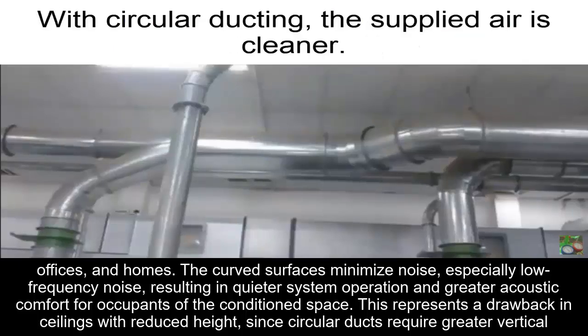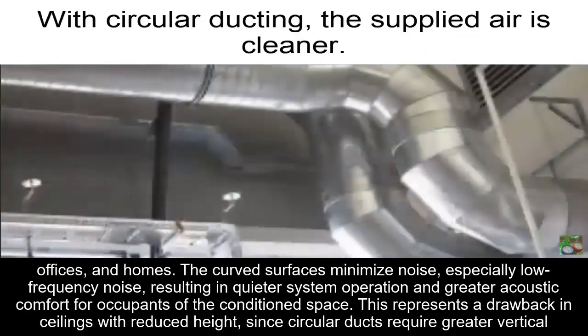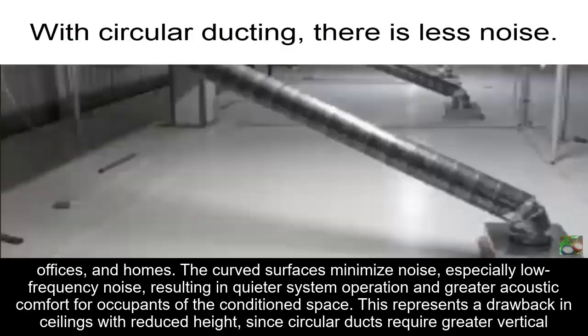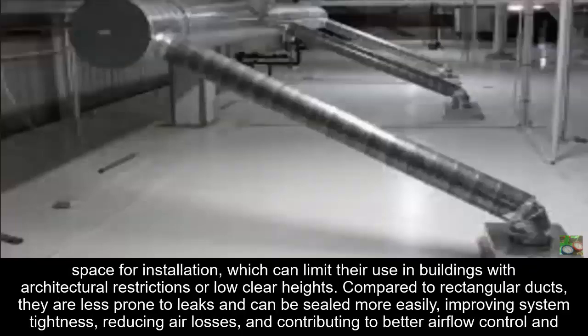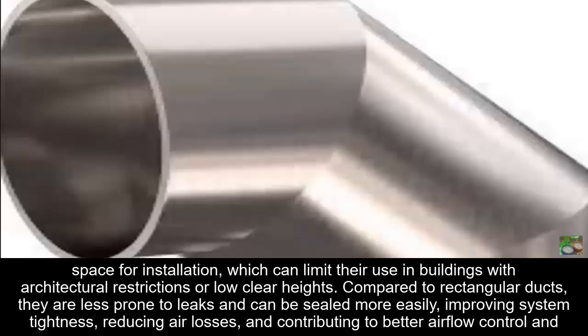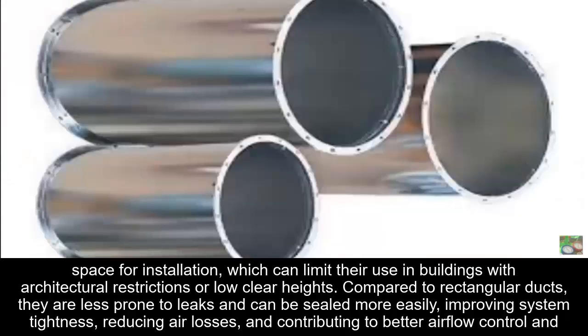The curved surfaces minimize noise, especially low-frequency noise, resulting in quieter system operation and greater acoustic comfort for occupants of the conditioned space. This represents a drawback in ceilings with reduced height, since circular ducts require greater vertical space for installation, which can limit their use in buildings with architectural restrictions or low clear heights. Compared to rectangular ducts, they are less prone to leaks and can be sealed more easily, improving system tightness, reducing air losses, and contributing to better airflow control and overall efficiency.